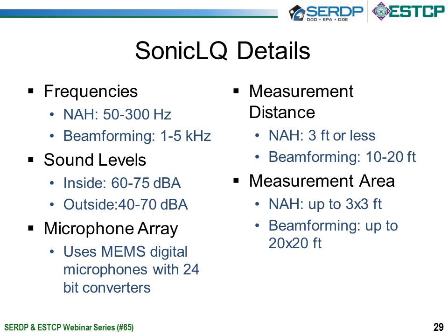So for a few of the details of the acoustics that are actually involved, the frequency range at which we do the low frequency near-field holography, the close-up measurements, is typically about 50 to 300 hertz. The frequency isn't just set to a single number. It will depend upon the background noise. If I have resonances in the building, that could become problematic. Is there something else that is a limitation in terms of modal structure inside the building that wouldn't give me even pressure? So I don't pick an exact number, but it's at fairly low frequencies. The beamforming that I use to look for any overall leakage or vibration is typically done on a much higher frequency range.